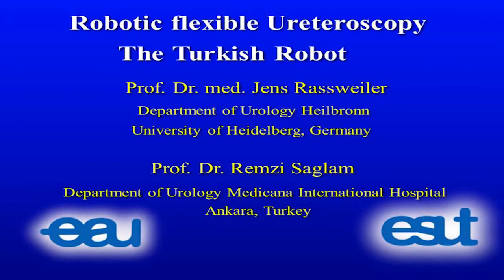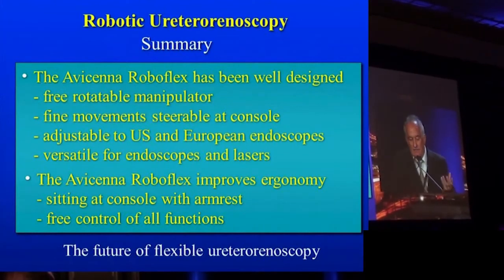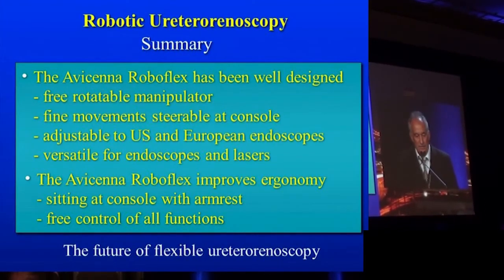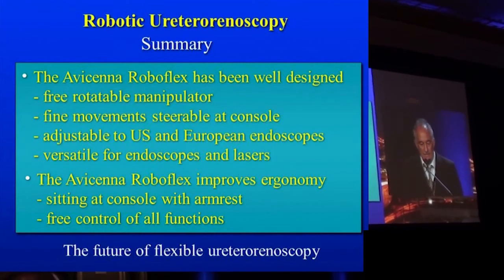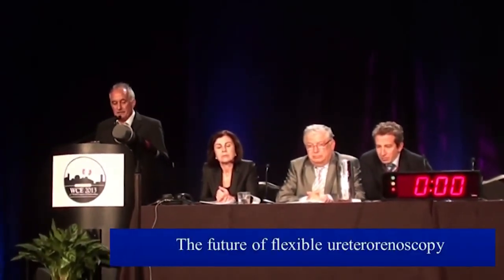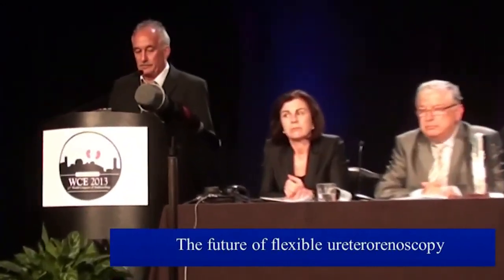In summary, the Avicina robot has been, in my view, a very well designed instrument — a free, rotatable manipulator with fine movements, steerable at the console, adjustable to US and European endoscopes, and versatile for endoscopes and lasers. The Avicenna Roboflex improves ergonomy significantly: sitting at the console with armrests, with free control of all functions. In my view, it is really the future of flexible ureteroscopy.